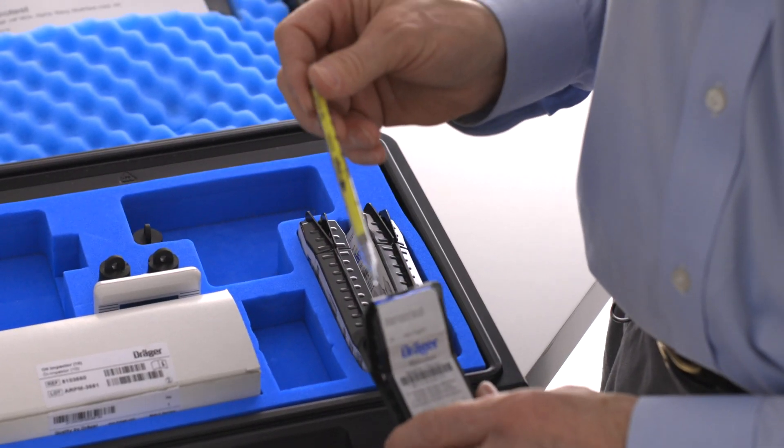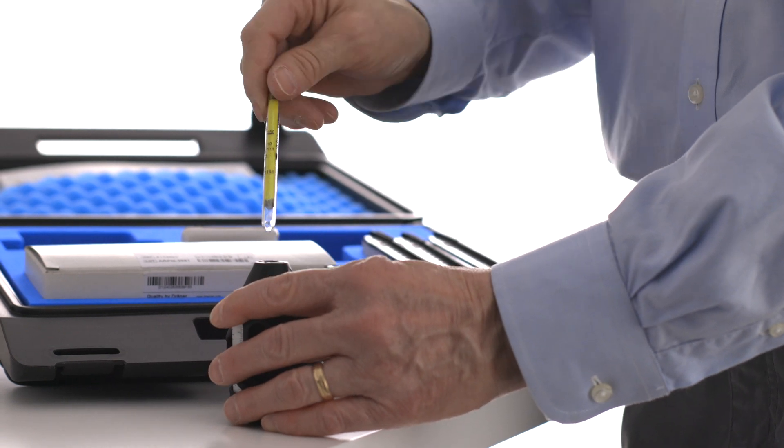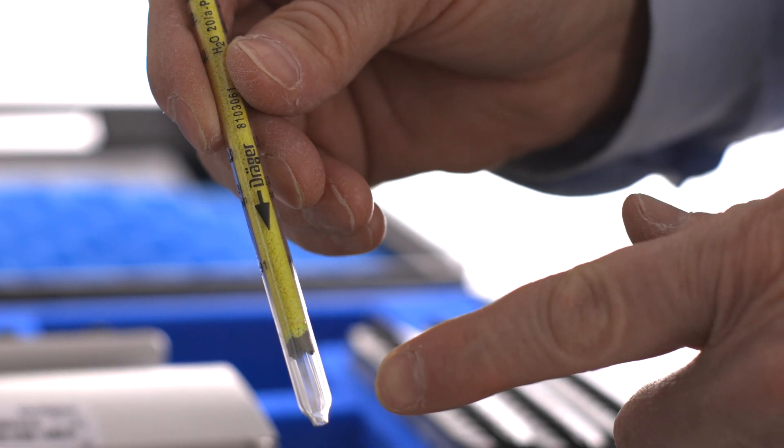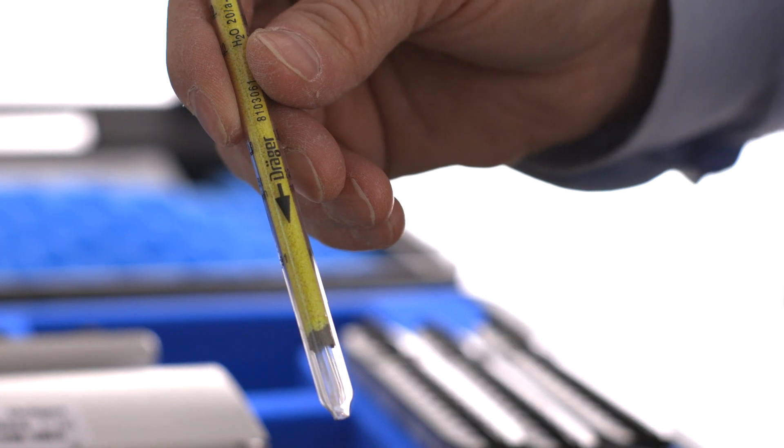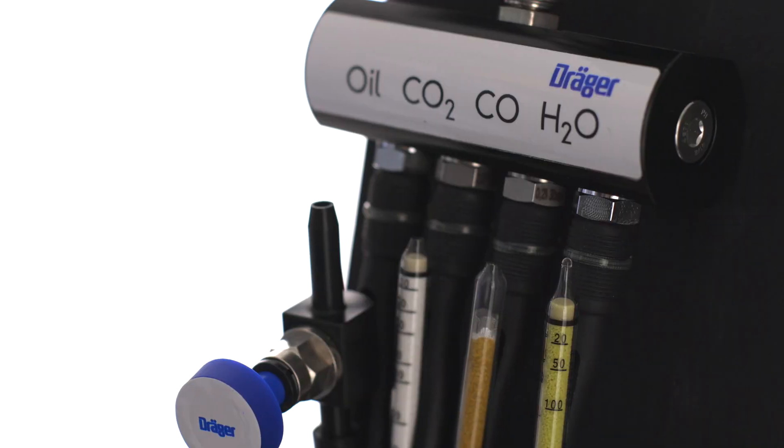Finally, take one of the water vapor tubes, but in this case we will only remove the tip from the outlet end of the tube, which is the end the arrow points towards. This tube is extremely sensitive to ambient humidity, so we won't remove the other tip until we are ready to start the test. Insert the tube into the holder, leaving the top part disconnected.